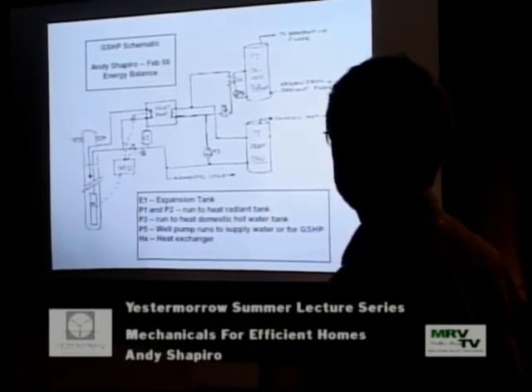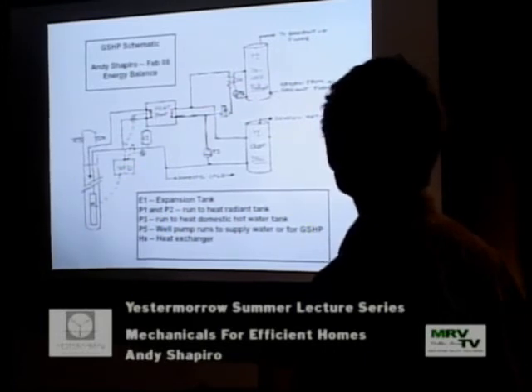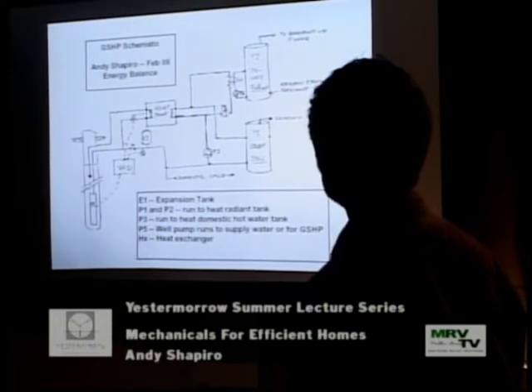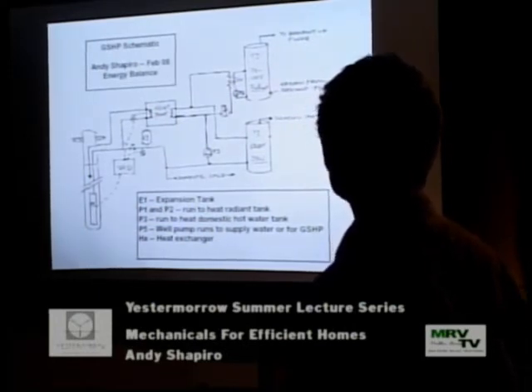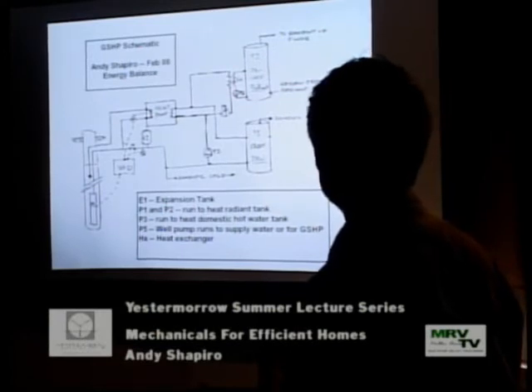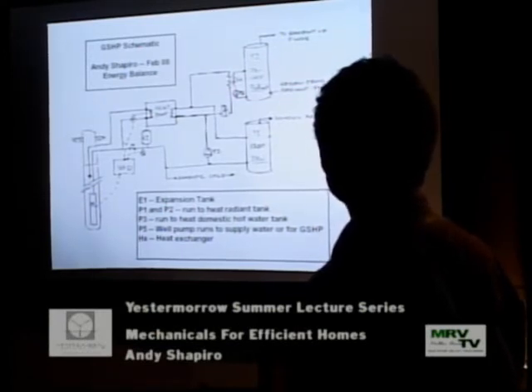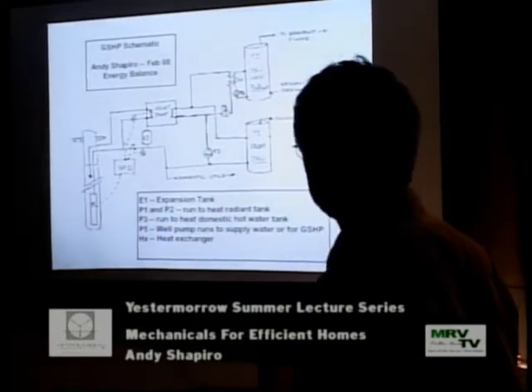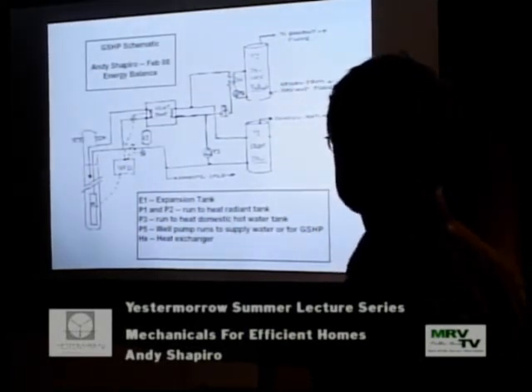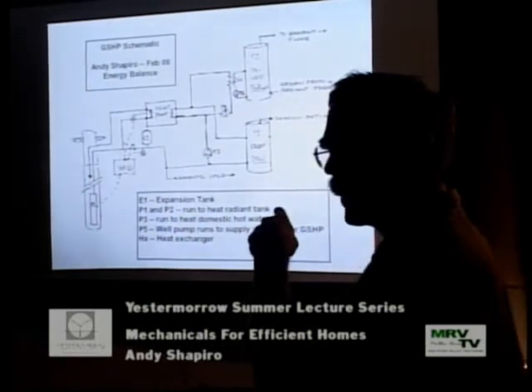Variable speed drive on the pump. The heat pump will heat one of 2 tanks. If the hot water tank is calling, it goes there first. If that tank's happy and there's a call for heat, it goes to the radiant zone. And again, you can see I separated them with a heat exchanger. I don't like mixing those two. And actually, that schematic is not all that complicated. But any question on that?